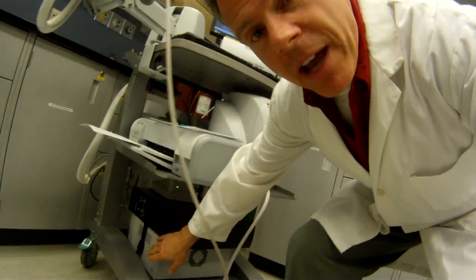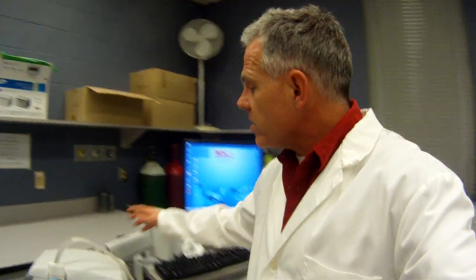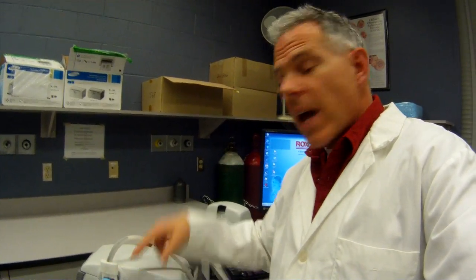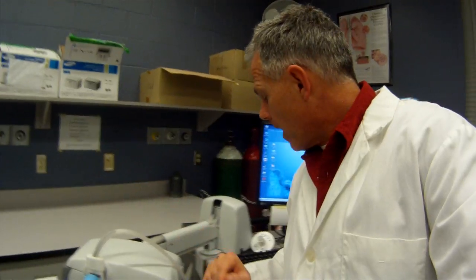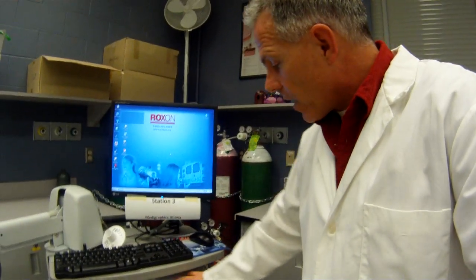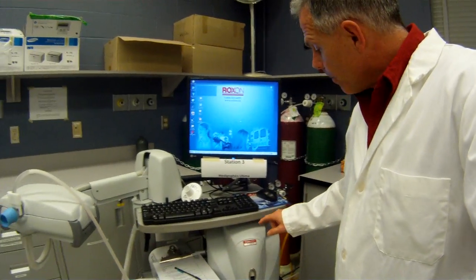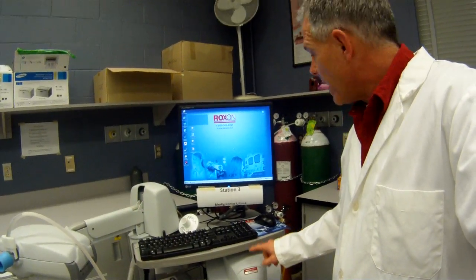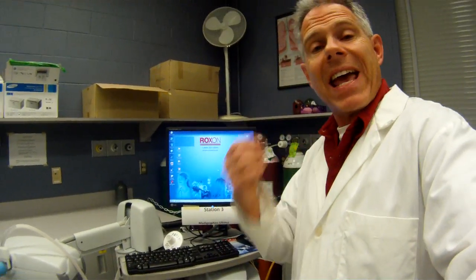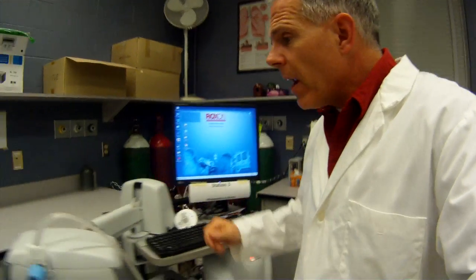Other than that, it's just a basic computer, and we have here our gas controlling unit. That's where the computer is hooked up and controls all the gases and controls this device right here, which is both our pneumotach and our gas controller. This big box right in here is our gas analyzer. That's how we can analyze the gases being breathed out by the patient for specific tests.